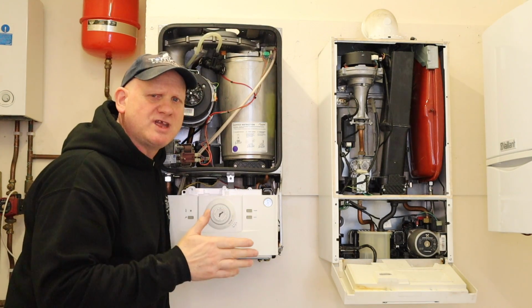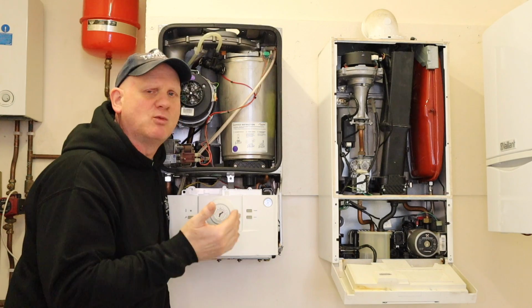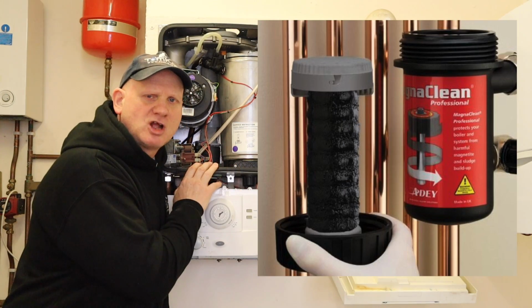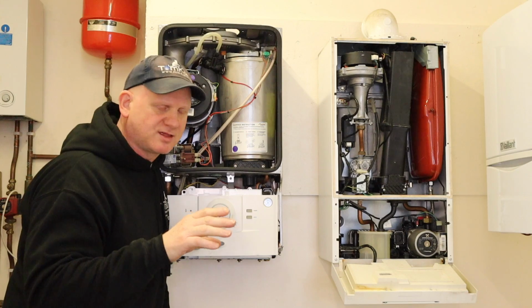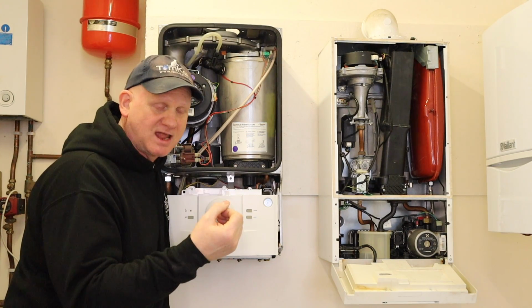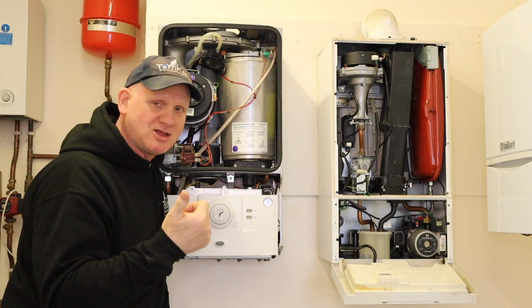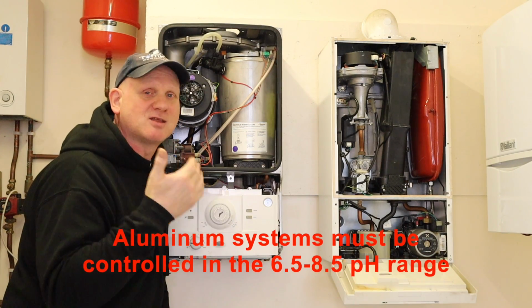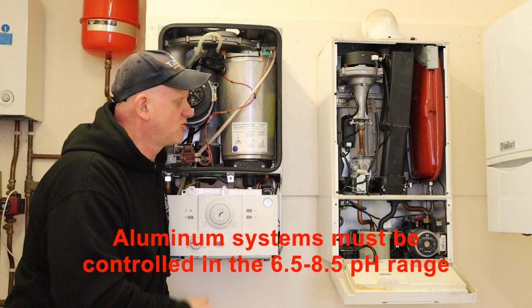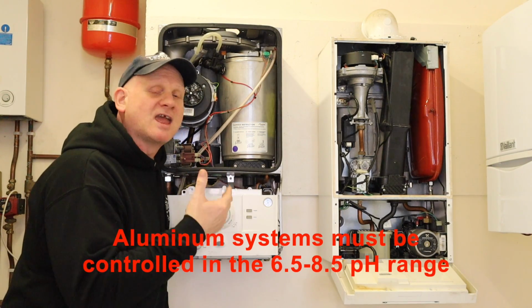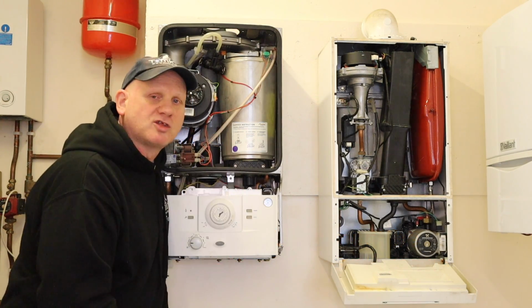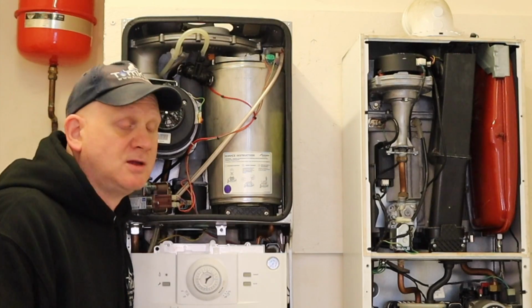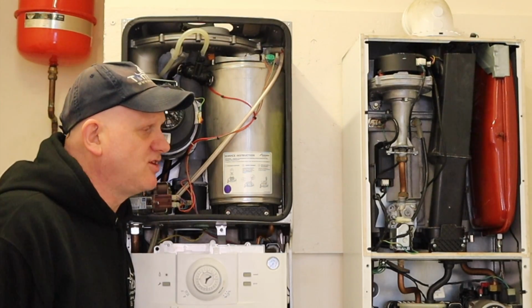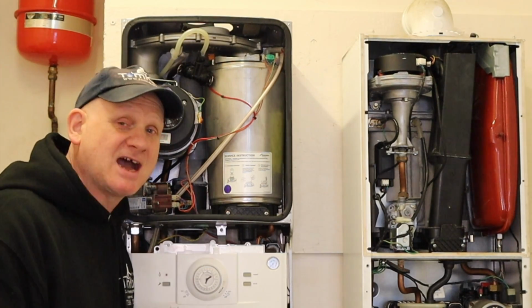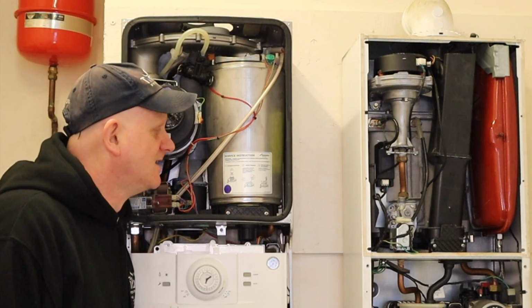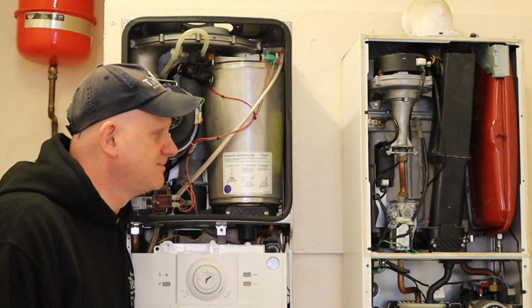So this is one of the major reasons why the regulations are changing, so that when boilers are installed, they must be installed with a magnetic filter and the water quality must be checked and kept up to date. It's important that the pH levels in the water, like we talked about before, are kept perfect for aluminium heat exchangers. And these magnetic filters take out the magnetite to stop these small waterways from getting blocked up. But like I say, the major pluses for these heat exchangers are they're a lot lighter, they can be cheaper in some cases, and they heat up incredibly quickly.